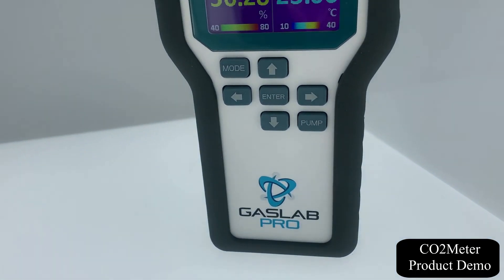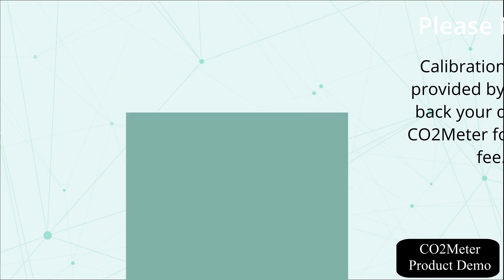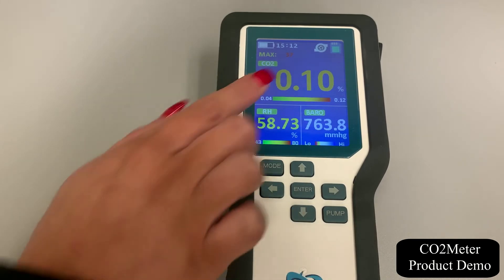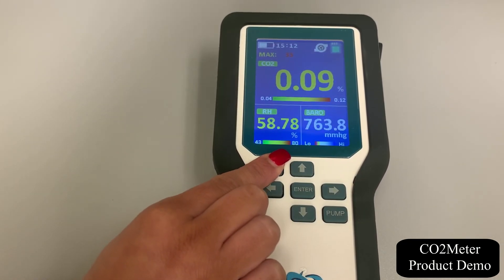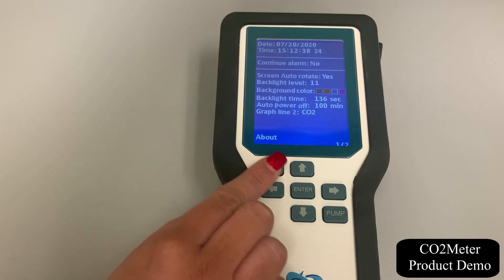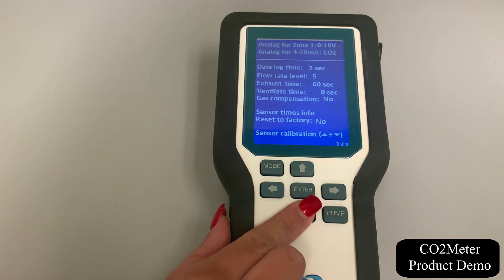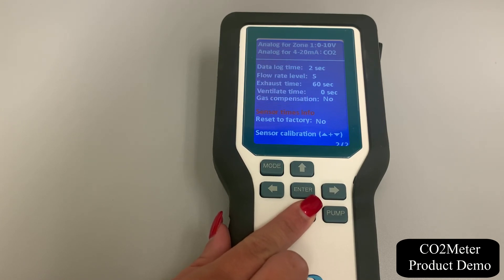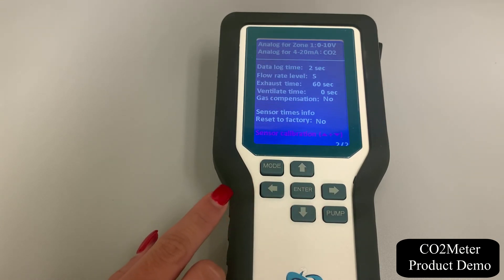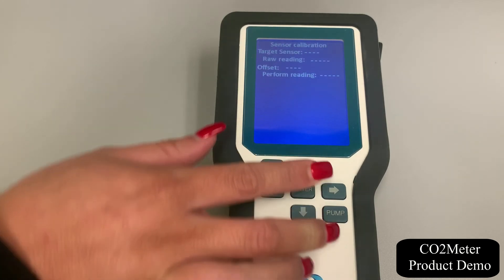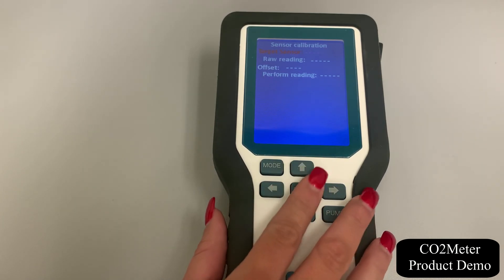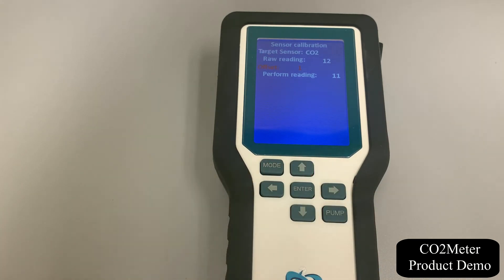One last key feature of this Multigas Sampling Data Logger is that it can be calibrated by the user by performing single point calibration. To get the calibration screen, enter the setup menu by turning on your device and pressing and holding down the mode button. Next, select the mode button again to see the second page of the settings screen where sensor calibration will be located. Press the down arrow key until sensor calibration is highlighted, then press and hold the up and down arrow keys at the same time to enter sensor calibration. Press enter to highlight the target sensor — the top line — in red, then press down to scroll through the available sensors.